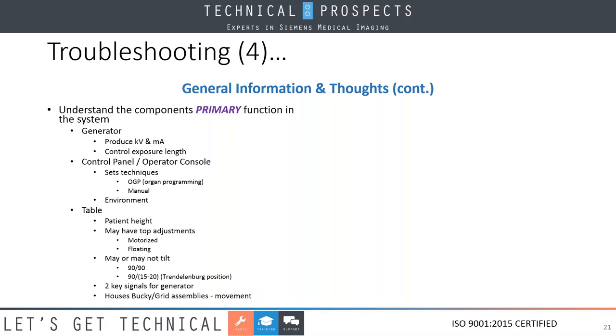Okay, now when we look at the table, here we set patient height, all right? They may have motorized or floating adjustments. Some tables tilt, some don't. If they do tilt, they can be 90-90 or 90-15-20, which is in Trendelenburg position, which means the head is lower than the foot.